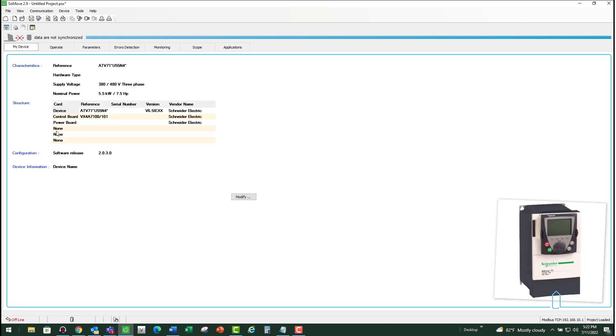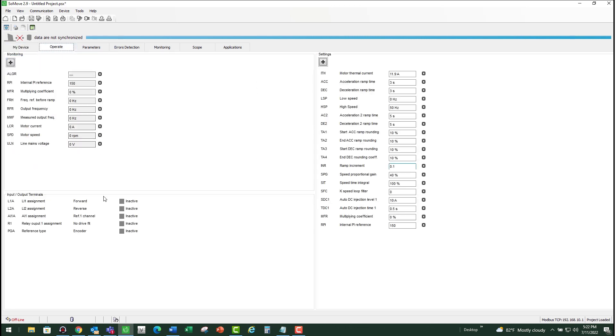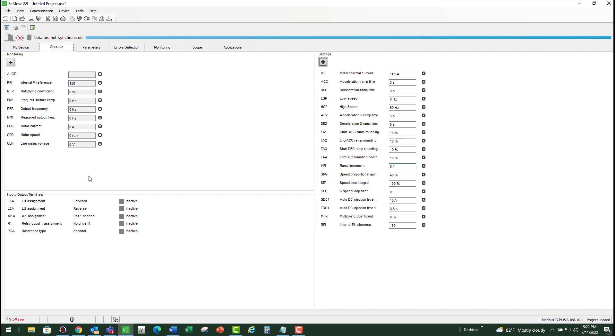You can also check and see what the VFD reads for the line voltage or the mains voltage. You can actually see it under the operate tab in SoMove and monitor what that line voltage is and compare that to your measured value. You also need to measure the DC bus voltage on the VFD itself and make sure that DC bus voltage is not too high. It should be approximately about 1.41 times your line voltage.